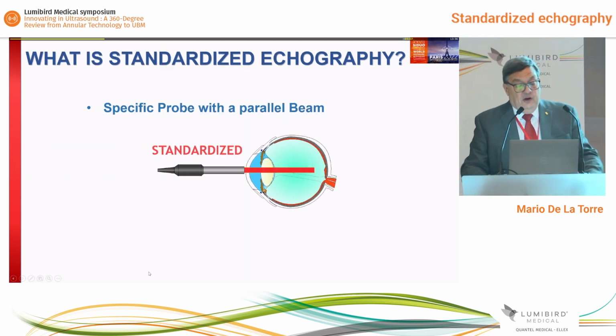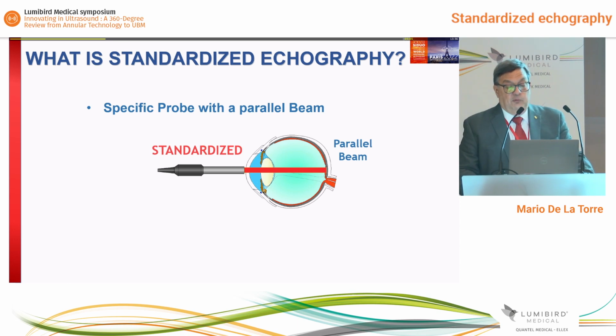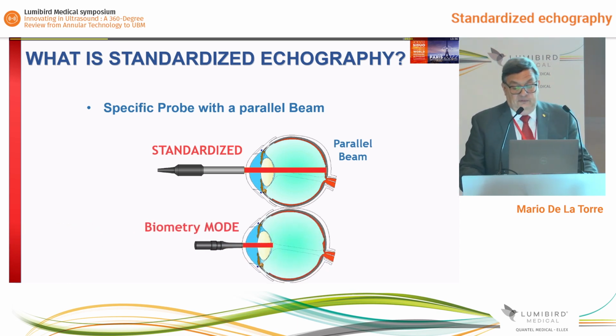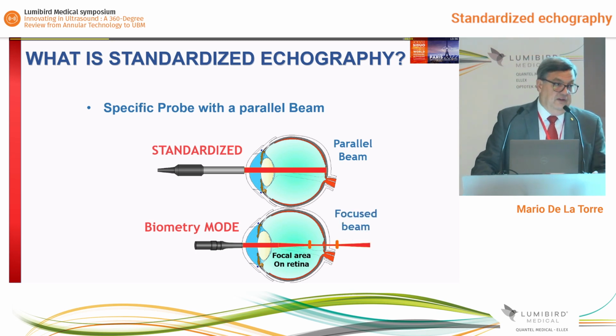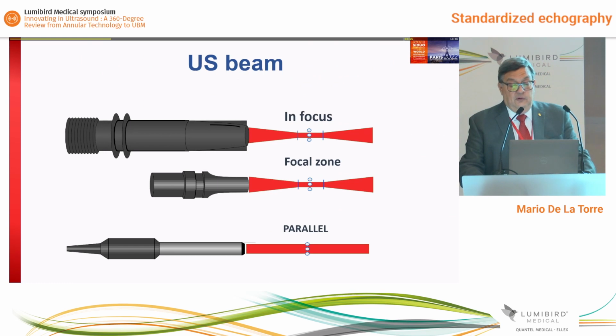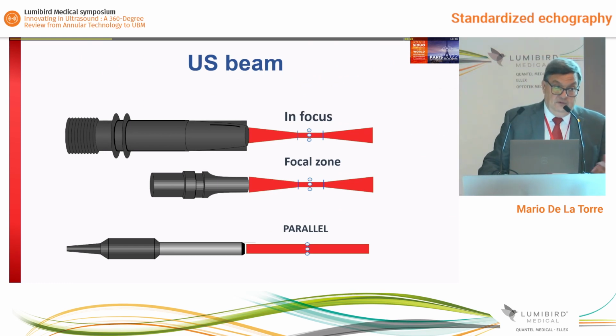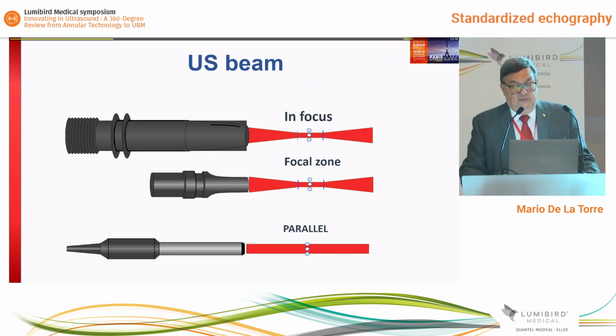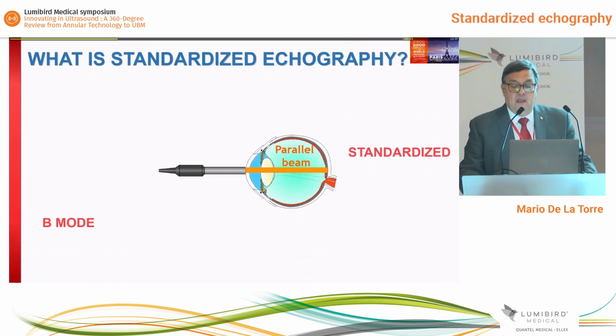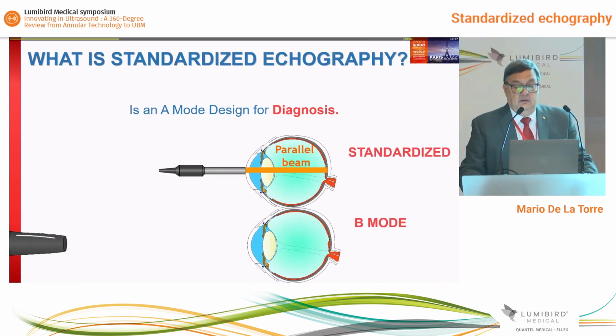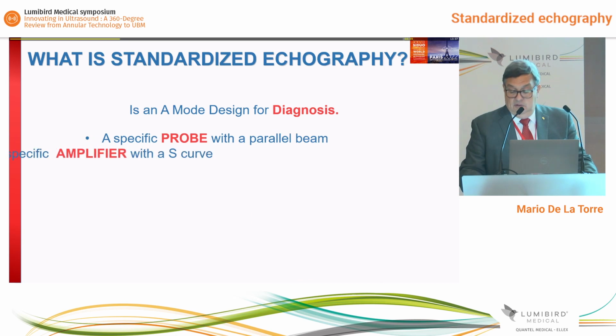But why? Because standardized is a specific probe with parallel beam, and biometry mode is focused in 23 millimeters, and there's a big difference. And also the ultrasound beam for the B mode is focused. Also, there is a focal zone in the biometry, but in A mode you have another way to do it with a parallel beam. Okay? The parallel beam, compared with the B mode, they are different.